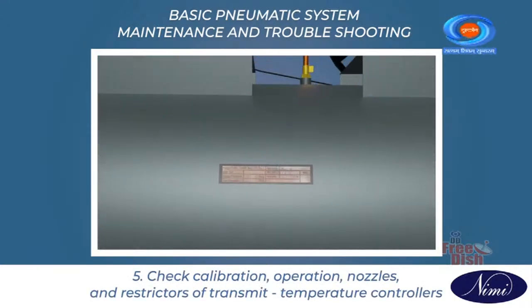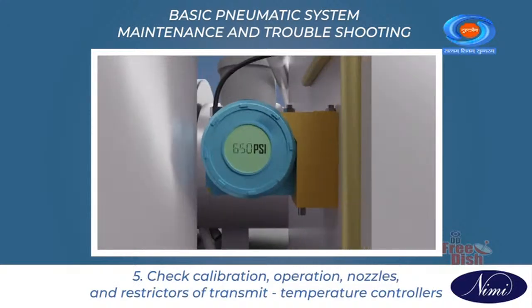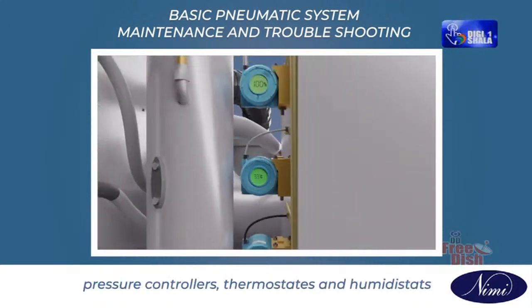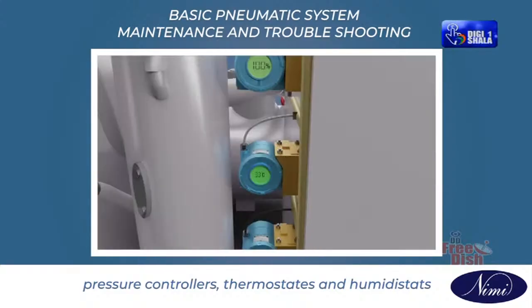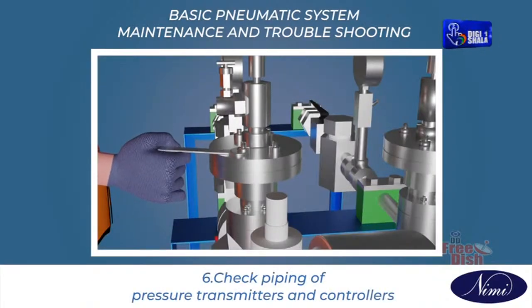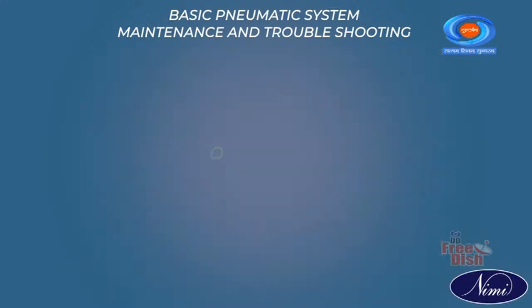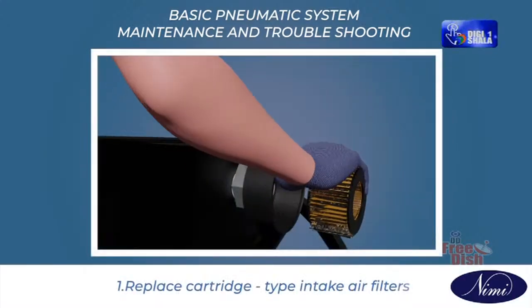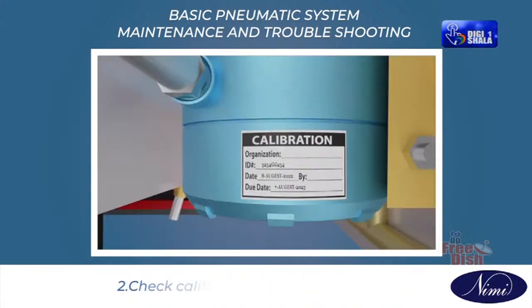Check calibration, operation, nozzles, and restrictors of transmit temperature controllers, pressure controllers, thermostats, and humidistats. Check piping of pressure transmitters and controllers. Clean elements and humidistats. Once in a year: replace cartridge type intake air filters. Check calibration of receiver controllers. Check valves for tight close-off.